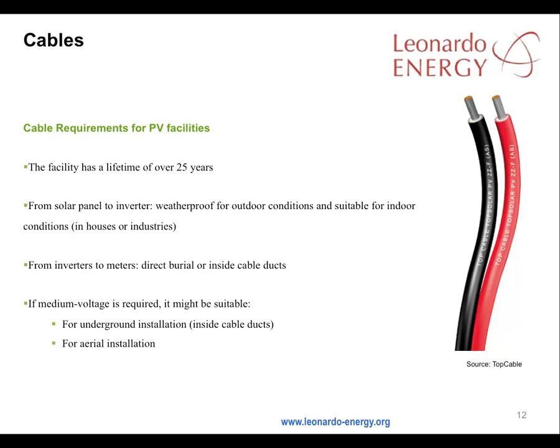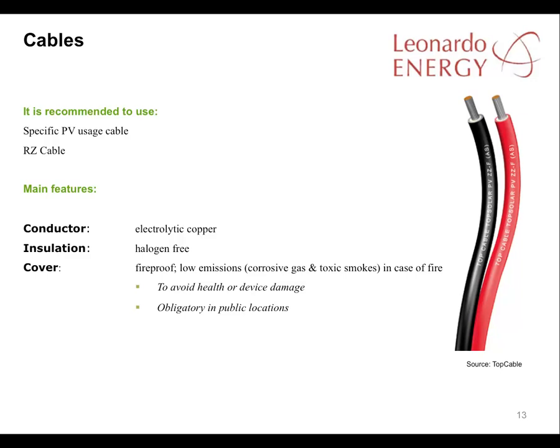Between inverters and meters, it's recommended that the cables are buried or run through cable ducts. In medium-voltage situations, there may be a case for aerial installation or, alternatively, run through cable ducts. There are cables specifically designed for PV applications, not always used by the leading developers. The cable's conductor should be electrolytic copper, the insulation should be halogen-free, and the cover should be fireproof with low emissions in case of fire to avoid health or device damage.